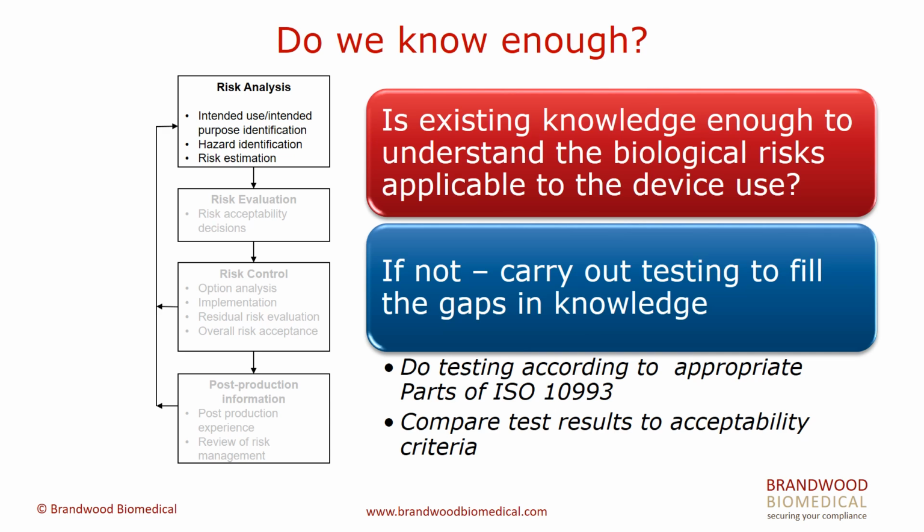We can then say, well, do we know enough? Have we established through the chemical characterization, from the literature, from a Part 17 analysis, that the leachables coming out of the medical device are within tolerable limits? If we can't establish that, we may then need to do testing to fill the gaps in our knowledge.